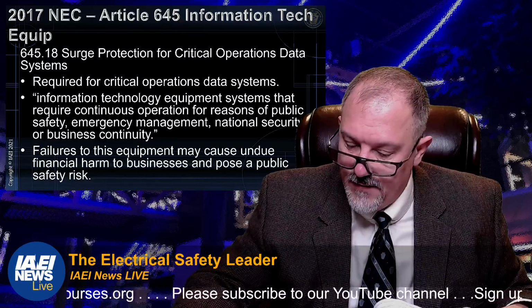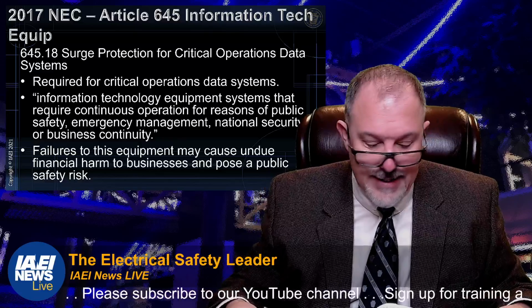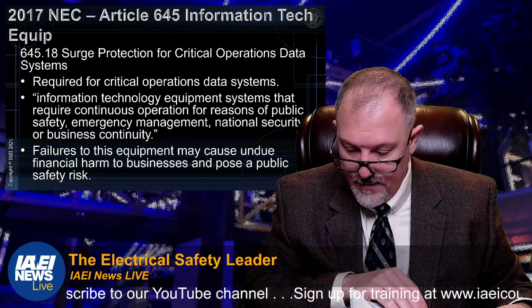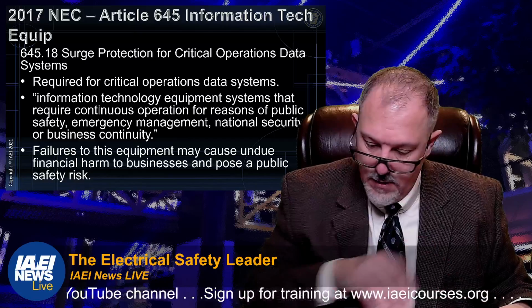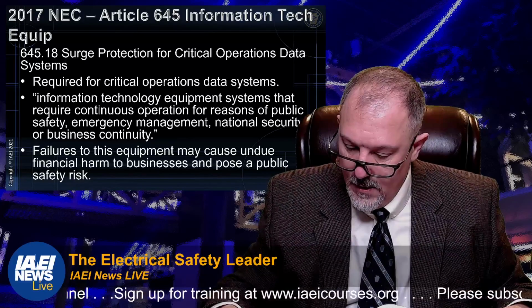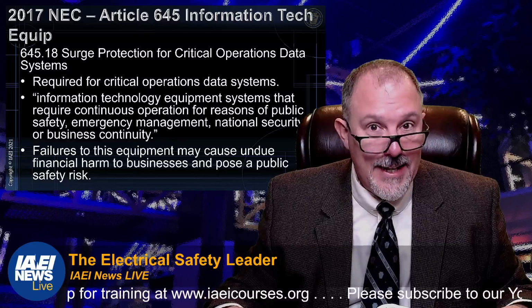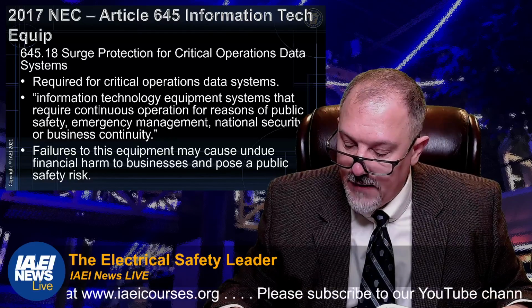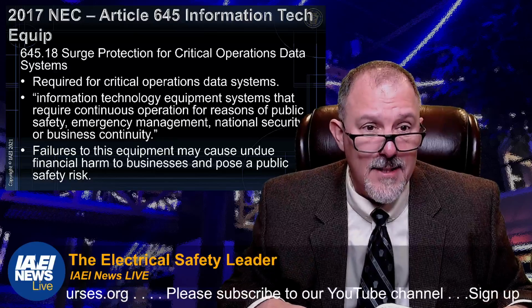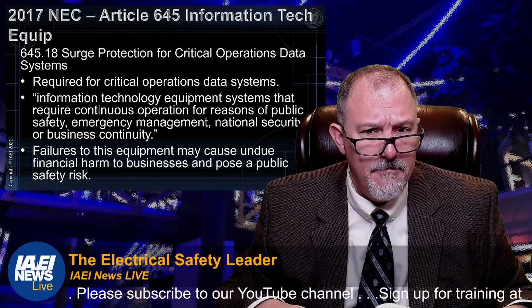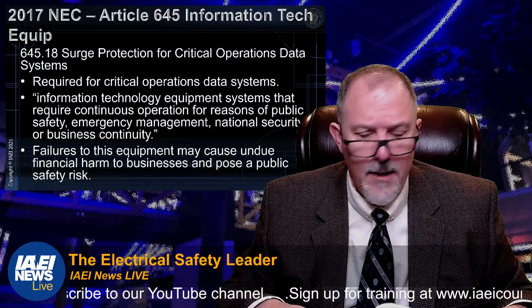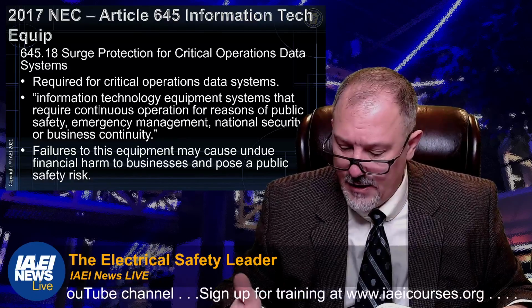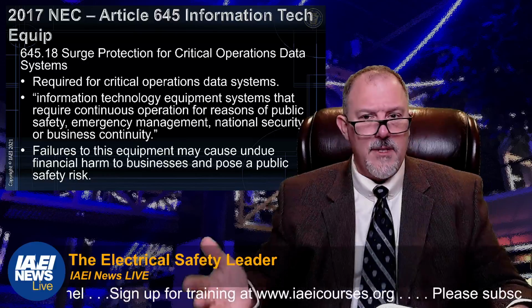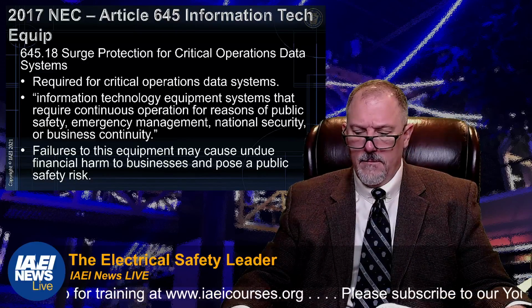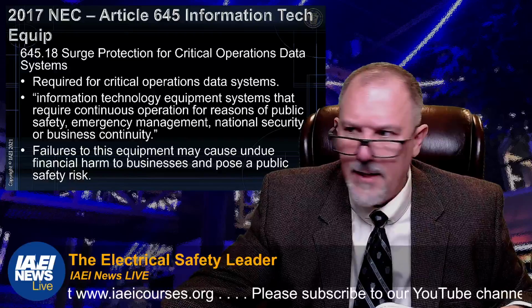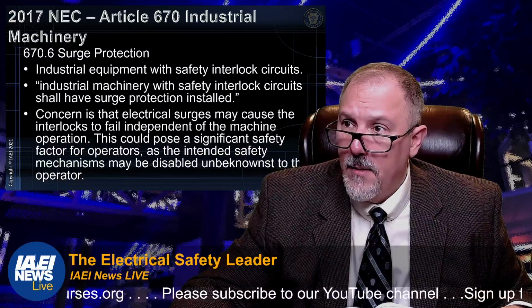645.18. What's 645.18? 645, I know is IT. Where's 645? Here we go. Surge protection for critical operation data systems. Listed surge protection shall be provided for critical operation data systems. That's pretty vague. Don't you think it should be provided for critical operation data systems? What does that mean? I think it needs to get a little love in the next cycle. That's what I think. Well, this is 17 code.